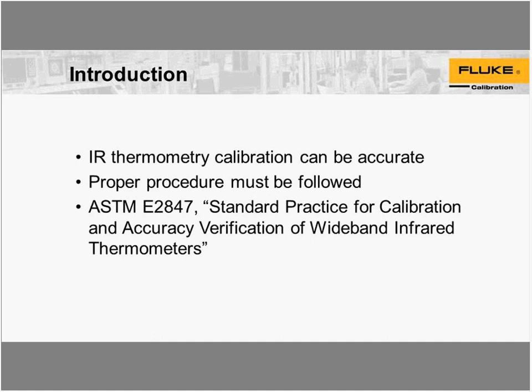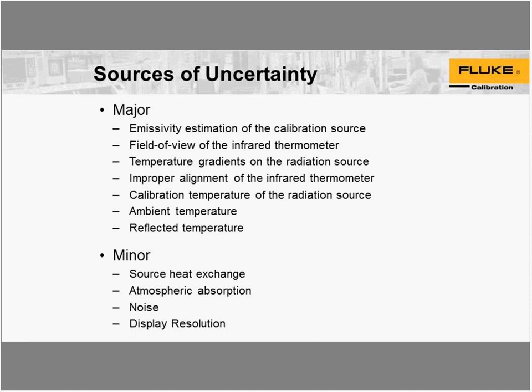Just for introduction: IR thermometry calibration can be accurate, but in order to be accurate, a proper procedure must be followed. Such a procedure is found in ASTM standard E2847, Standard Practice for Calibration and Accuracy Verification of Wideband Infrared Thermometers. Much of the presentation today is based off of this standard.